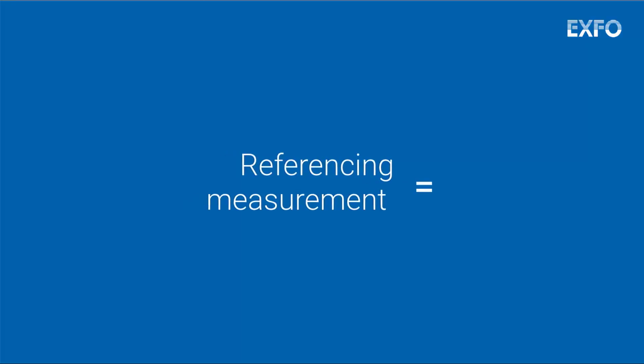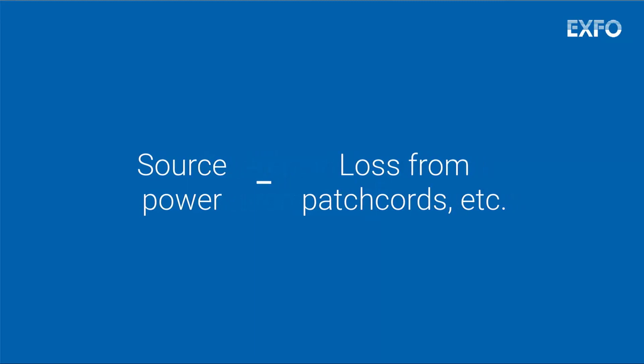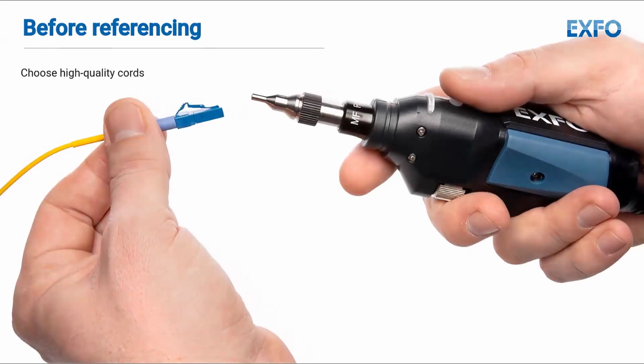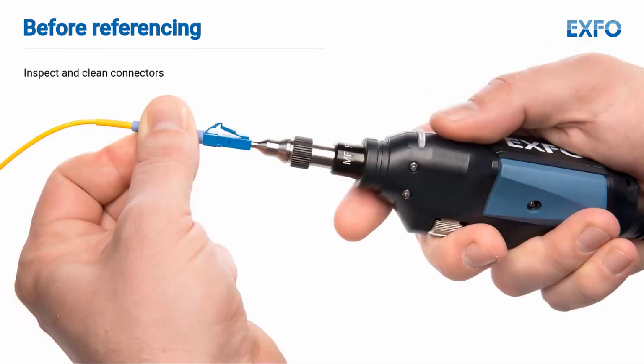The referencing measures and stores the value of the source power, minus the loss of the various patch cords and connectors required to do the measurement. Before doing any referencing though, make sure you have high-quality test cords, and that all connectors are inspected and clean.